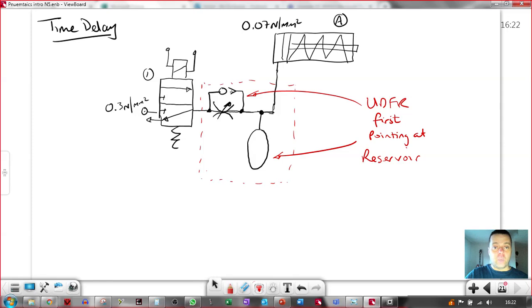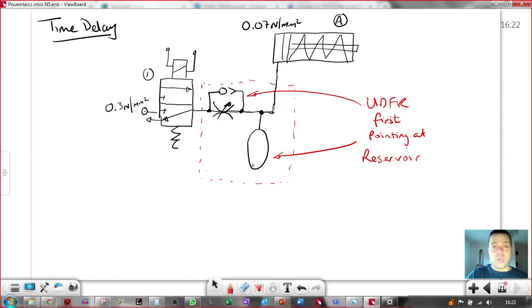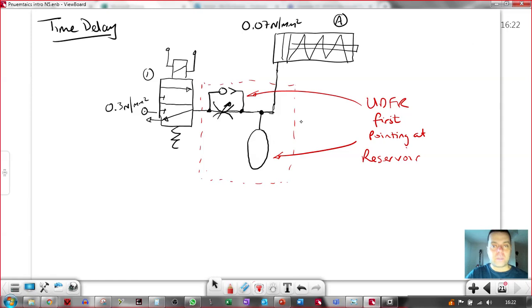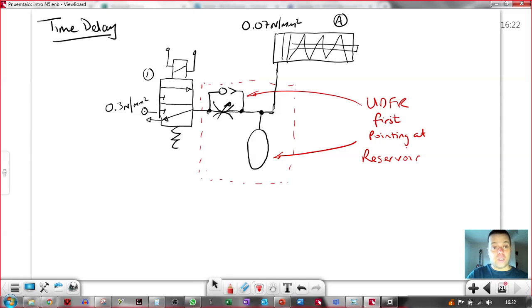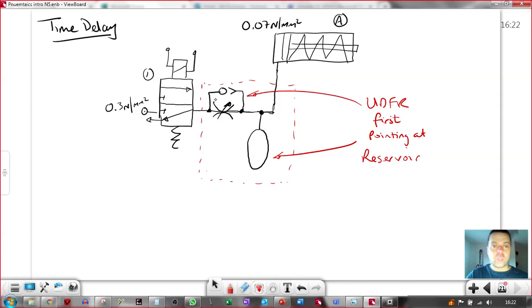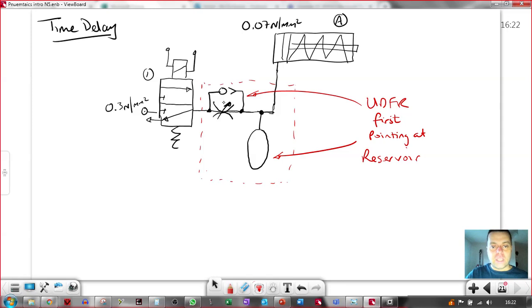If you put this the wrong way round, and the restrictor pointing this way, then you'll get full flow through here. And the reservoir will fill up almost immediately, and you'll get no restriction. But then when the solenoid de-actuates and the spring tries to push the cylinder back, you'll be forcing the exhaust air through the restrictor. So it will be a speed controlled in-stroke if you accidentally put that the wrong way round.